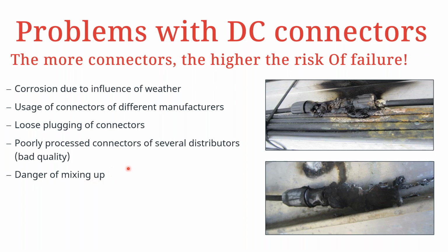So these photos show us the typical failures. These are very high risk for fires. So you can imagine if the material around this MC4 plug was easily ignited, then a fire was imminent in this particular failure case.